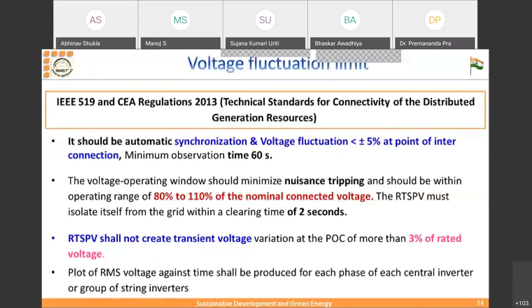Nowadays the inverters take care of this. If there is a fluctuation in the voltage, the inverter will get tripped. This is a huge problem in our country. If you install a solar power plant in Gujarat, you have to reduce the voltage limits, and if you are installing a solar plant in Bihar or Uttar Pradesh, you have to increase the voltage limits of solar inverters. So there are two standards.